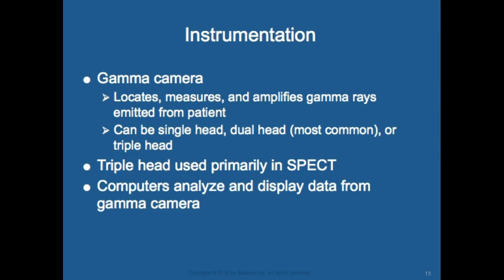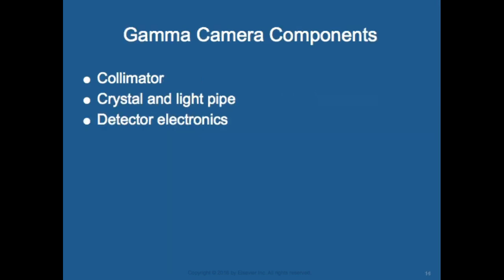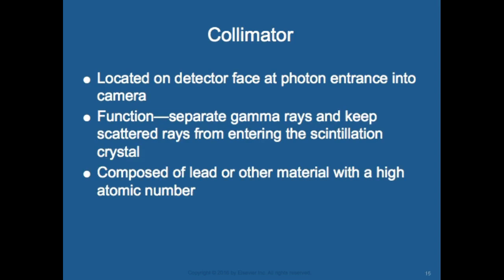A gamma camera localizes, measures, and amplifies gamma rays emitted from the patient. It can be single head, dual head (the most common in facilities nowadays), or triple head, which is usually used in SPECT. Computers analyze and display data from gamma cameras. The components of a gamma camera are the collimator, crystals and light pipes, and detector electronics. The collimator is located on the detector face at the photon entrance.